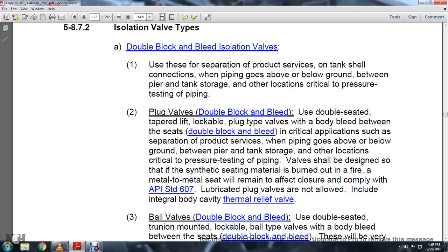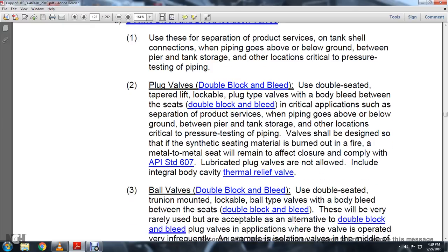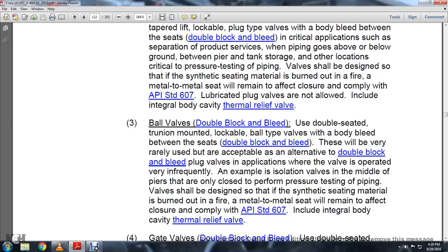The valve should be designed so that if the synthetic seating material is burned out in a fire, the metal to metal seat will remain an effective closure, complying with API Standard 607. Lubricated plug valves are not allowed. Include the integral body thermal relief valve.